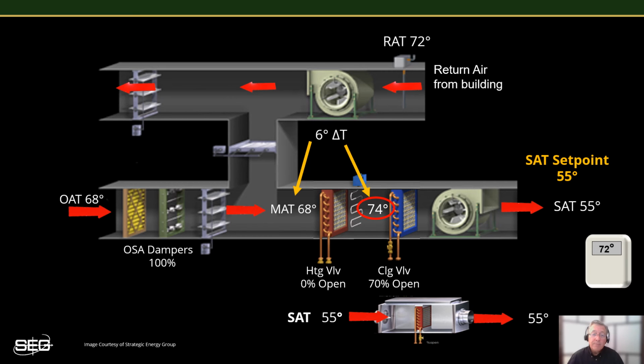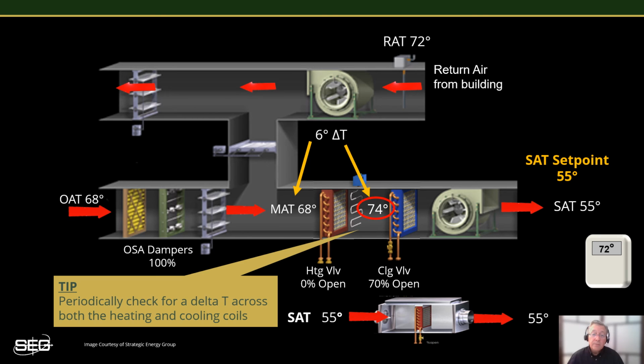So what you need to understand is that this is an issue that's very easy to overlook. This form of simultaneous heating and cooling, where the cooling load is artificially increased by leaky heating valves and then automatically covered up, oftentimes happens unbeknownst to the untrained eye, and it frequently goes on for years. This is why it's so important to regularly scrutinize the system temperatures, keeping an eye out for things like leaky heating and cooling valves, causing simultaneous heating and cooling in your systems.